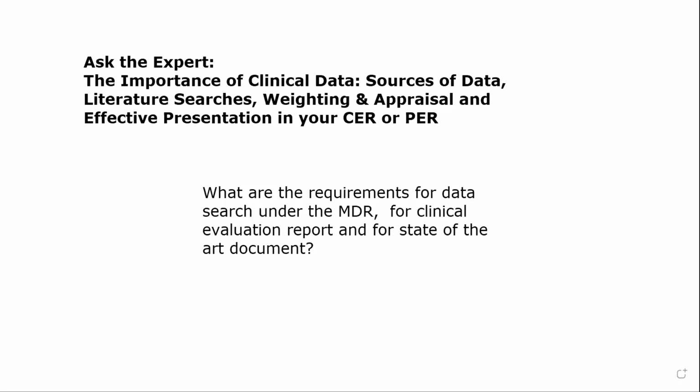So in my nomenclature, if we're talking about MDR and state-of-the-art, for those of you from the IVD space out there, be thinking of your SVR and be thinking of then how that translates into your PER, because you're going to have to repeat that scientific validity and state-of-the-art in your PER.